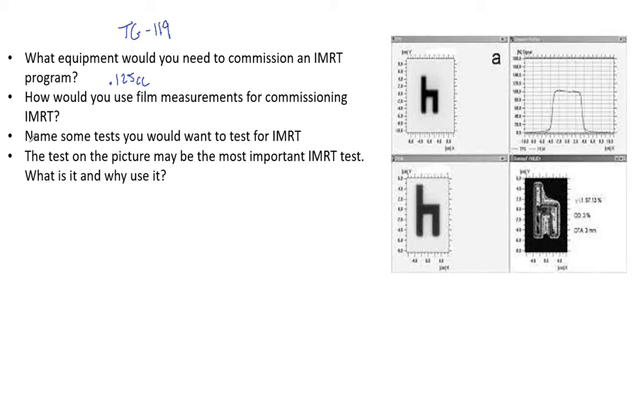There are a lot of tests you can do, and you want to range them in terms of difficulty. Start very easy — that way if something doesn't look right it's easily fixed and you don't have a lot of variables. For example, simply an AP/PA: you look at the central dose with a chamber and use film for gamma analysis, something very simple. Then you can do parallel opposed fields, which is still pretty easy.